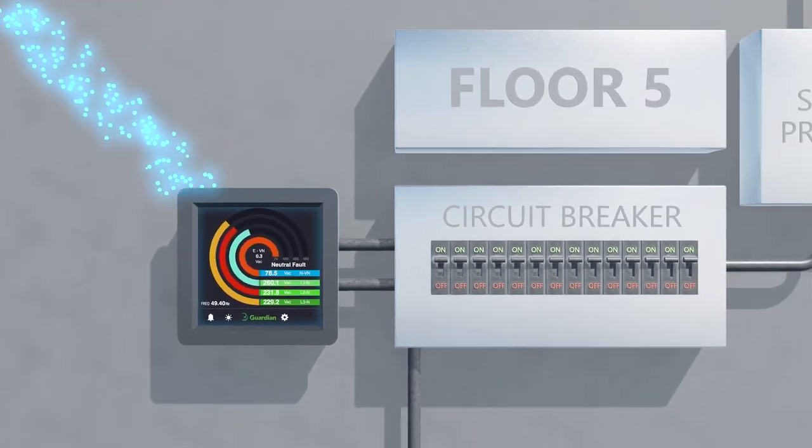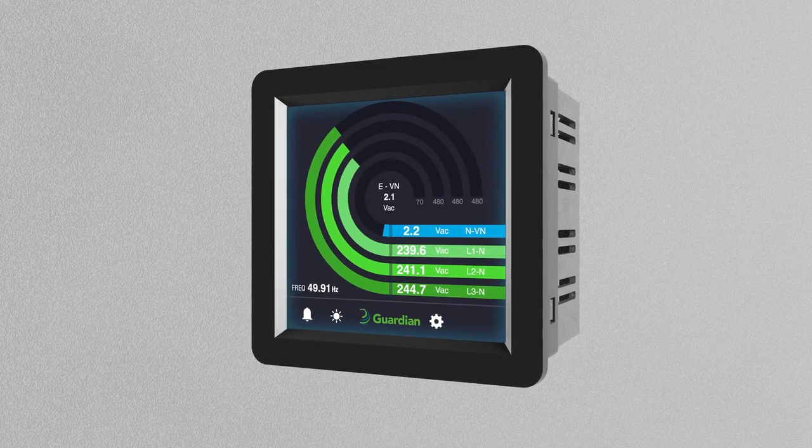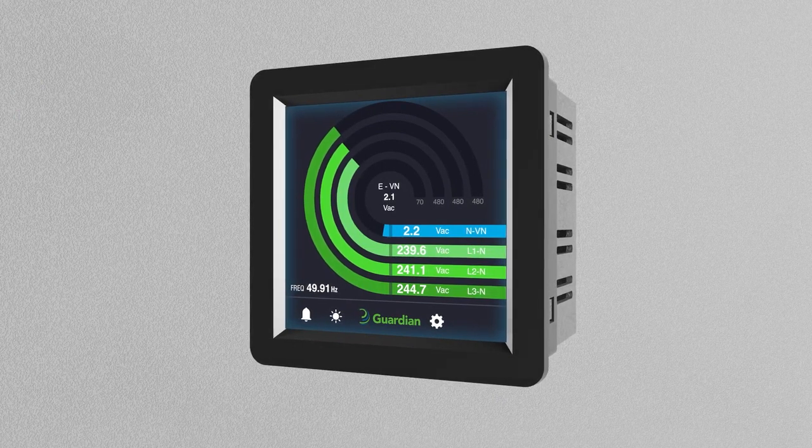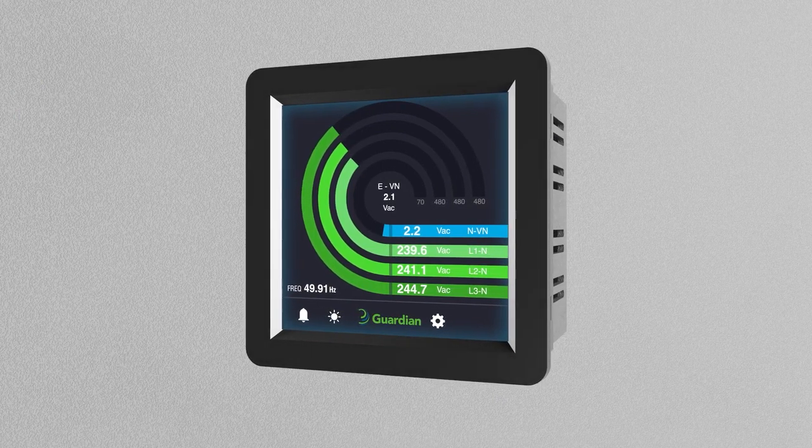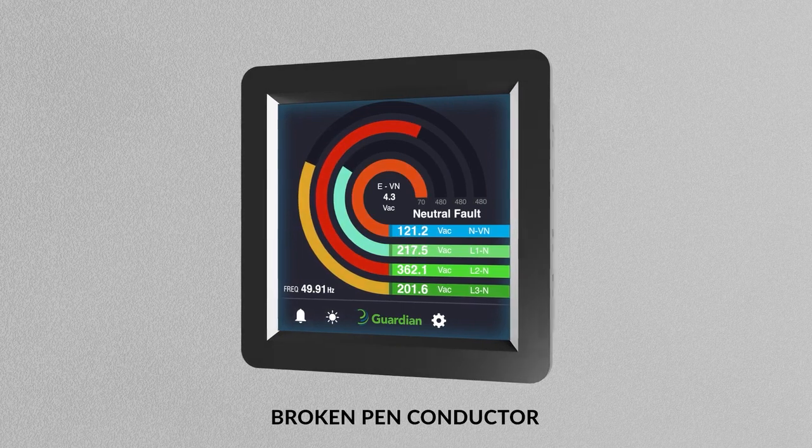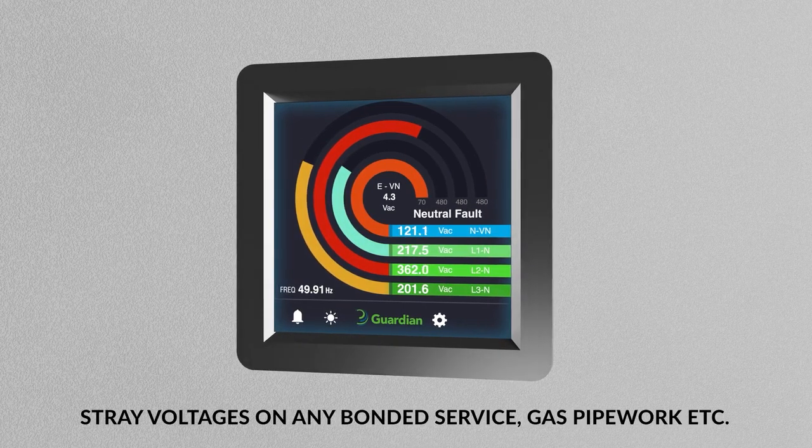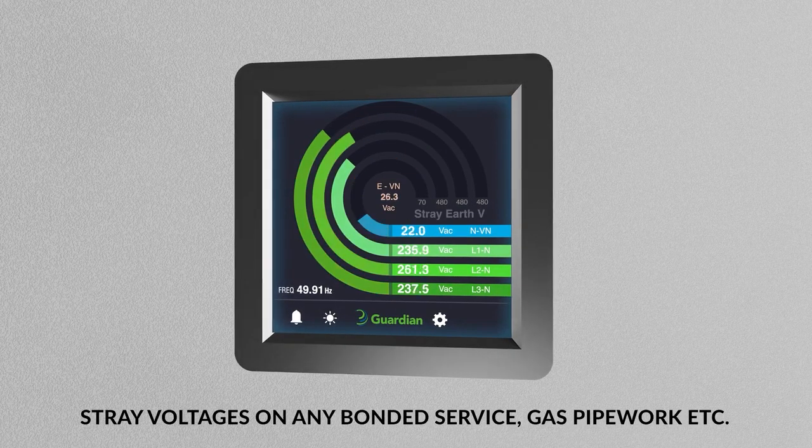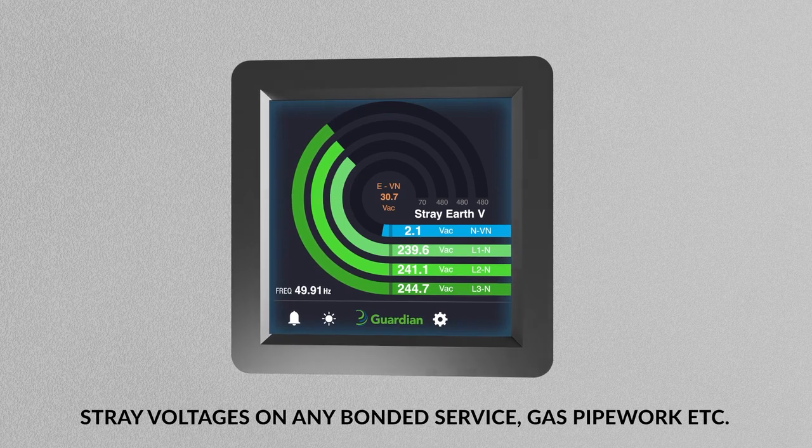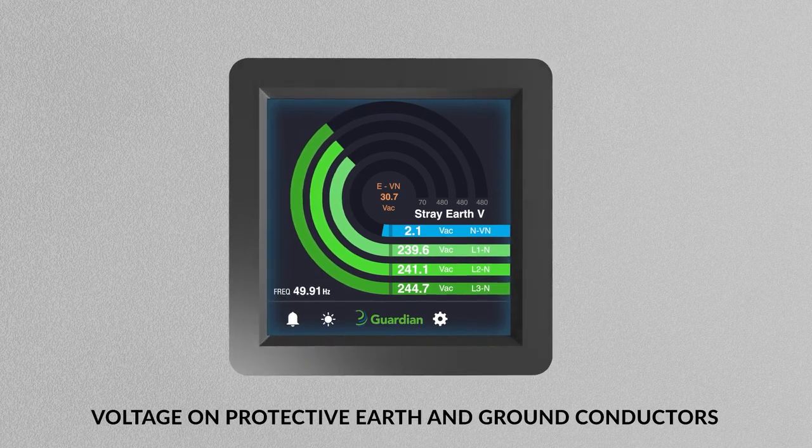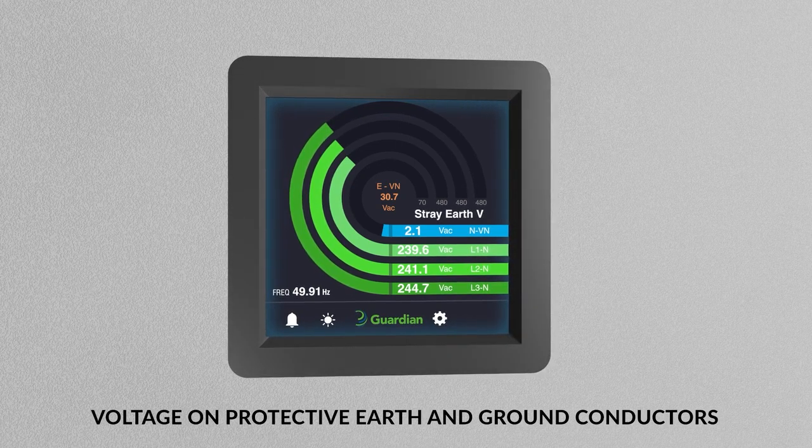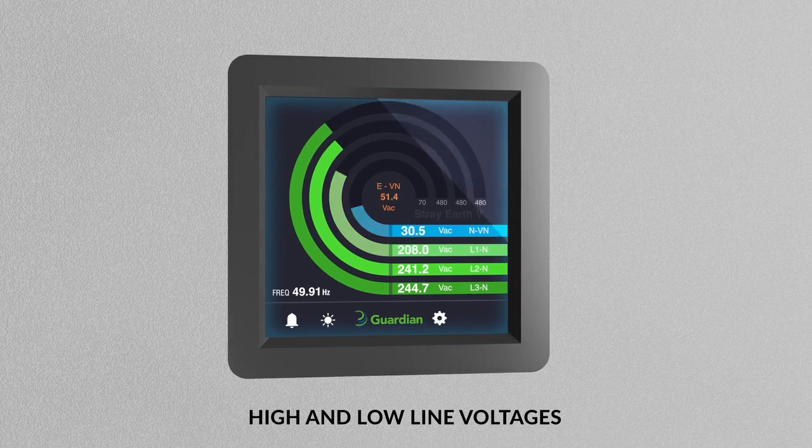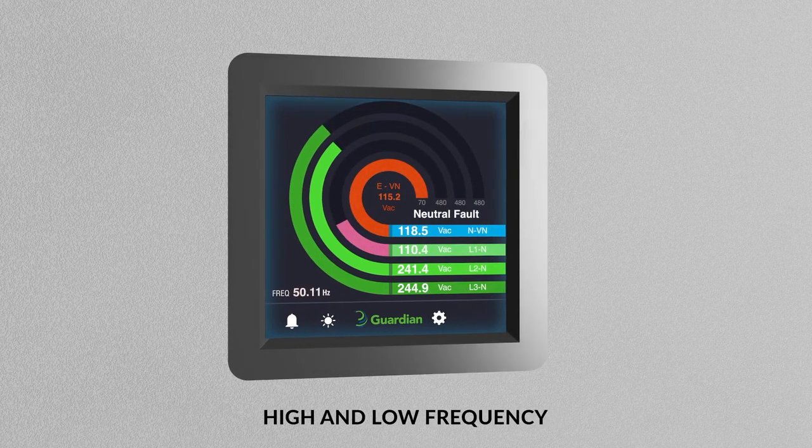The Guardian incorporates the patented OPEN technology and can detect faults including loss of neutral, broken PEN conductor, stray voltages on any bonded service including gas pipework, voltage on protective earth and ground conductors, high and low line voltages, and high and low frequency.